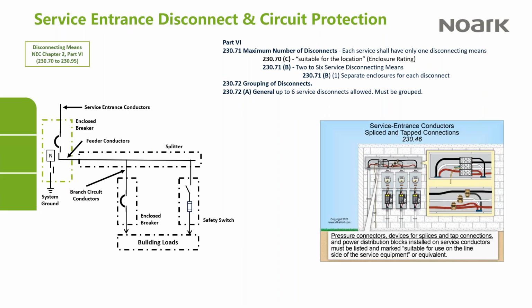Then it goes on to say there's an exception, which means that you can have up to 6 service disconnecting means. And the way this works is the service, as you see in this picture, comes up into a splitter first. That splitter must be rated as a service entrance device. I think it's actually the terminals inside. But then you can have multiple service disconnects on the output side of that splitter box. Okay. When those disconnects are being grouped together, they must be mounted together in a group. And again, there's some exceptions, but generally speaking, you need to mount them all together in one place.